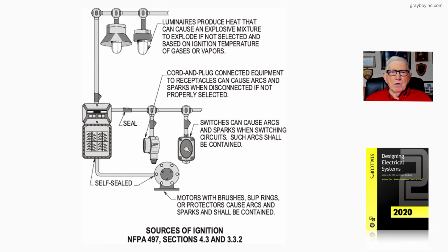And of course, an explosion-proof enclosure that you see in this illustration, 21-15, notice that this enclosure will contain an explosion, but the hot gases escape through the escape path or the flame path, which is a width, a height, and a length.